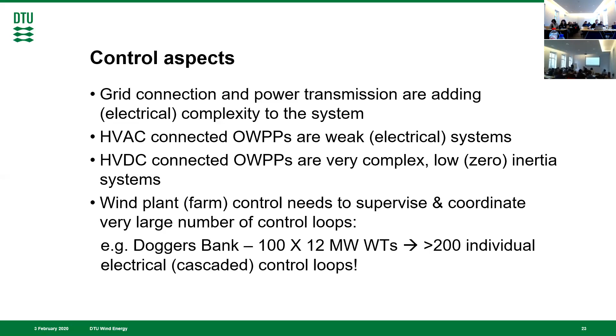Another interesting aspect from a control perspective: if we talk about wind plant and farm control, without even including the flow modeling part, just looking at the electrical side, you have to supervise and coordinate a very large number of control loops. Take Dogger Bank as an example, expected to have around 100 wind turbines per plant at 12 megawatts each, meaning more than 200 individual cascaded control loops. All these loops have to be coordinated by a wind farm or wind plant control.